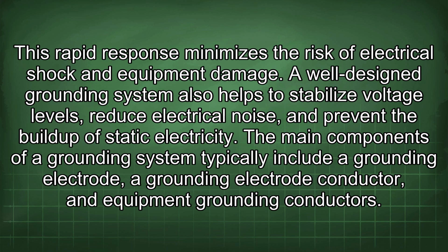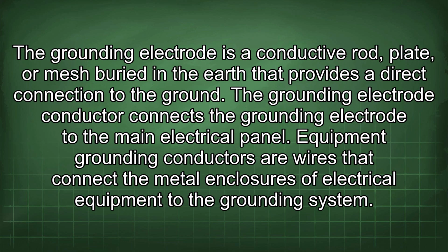A well-designed grounding system also helps to stabilize voltage levels, reduce electrical noise, and prevent the buildup of static electricity. The main components of a grounding system typically include a grounding electrode, a grounding electrode conductor, and equipment grounding conductors. The grounding electrode is a conductive rod, plate, or mesh buried in the earth that provides a direct connection to the ground. The grounding electrode conductor connects the grounding electrode to the main electrical panel.